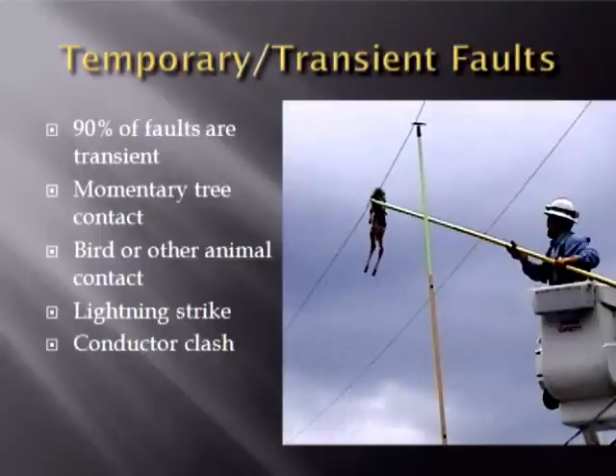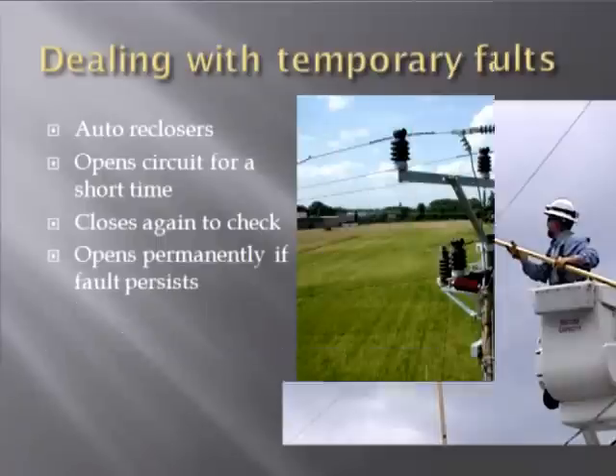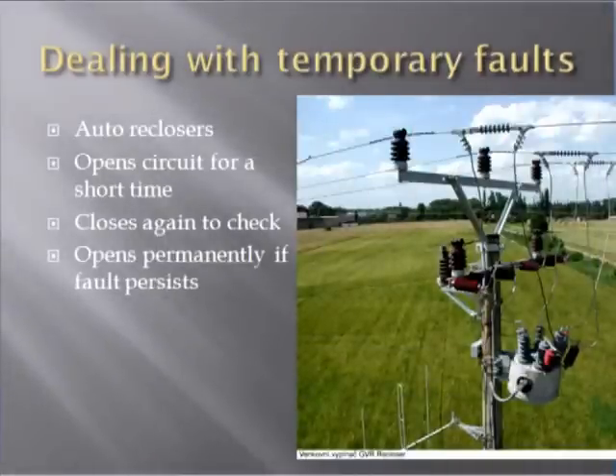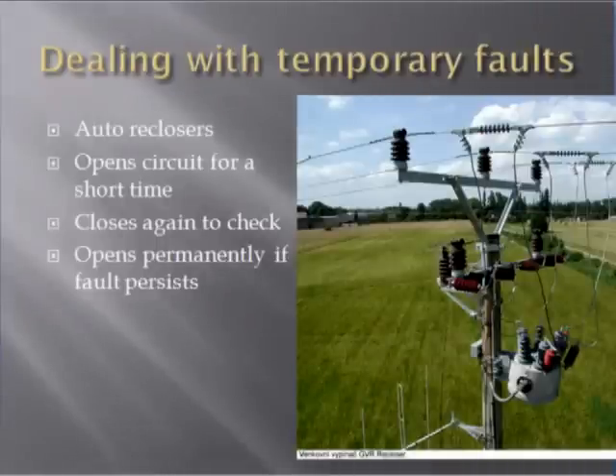How do we deal with this temporary fault? We can use a circuit breaker, but the disadvantage is that it has to be manually closed. If such a fault occurs in a remote area, it will take a long time to restore power. As such faults are quite frequent, a better solution is the auto recloser. In a power distribution system, a recloser is a circuit breaker equipped with a mechanism that can automatically close the breaker after it has been opened due to a fault. Since many transient faults clear themselves, a recloser improves service continuity by automatically restoring power to the line.